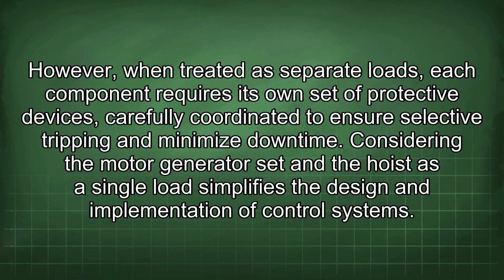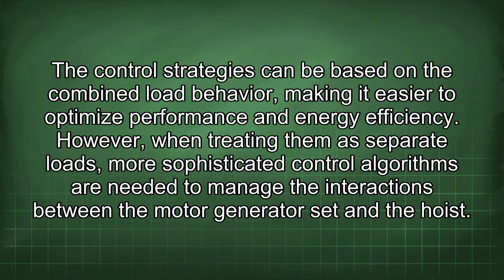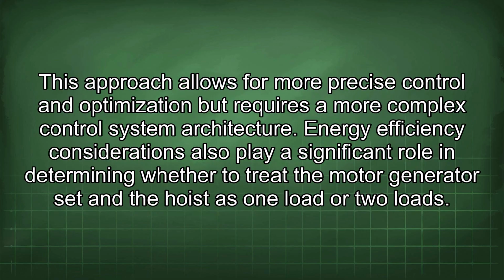However, when treated as separate loads, each component requires its own set of protective devices, carefully coordinated to ensure selective tripping and minimize downtime. Considering the motor generator set and the hoist as a single load simplifies the design and implementation of control systems. The control strategies can be based on the combined load behavior, making it easier to optimize performance and energy efficiency. However, when treating them as separate loads, more sophisticated control algorithms are needed to manage the interactions between the motor generator set and the hoist. This approach allows for more precise control and optimization, but requires a more complex control system architecture.